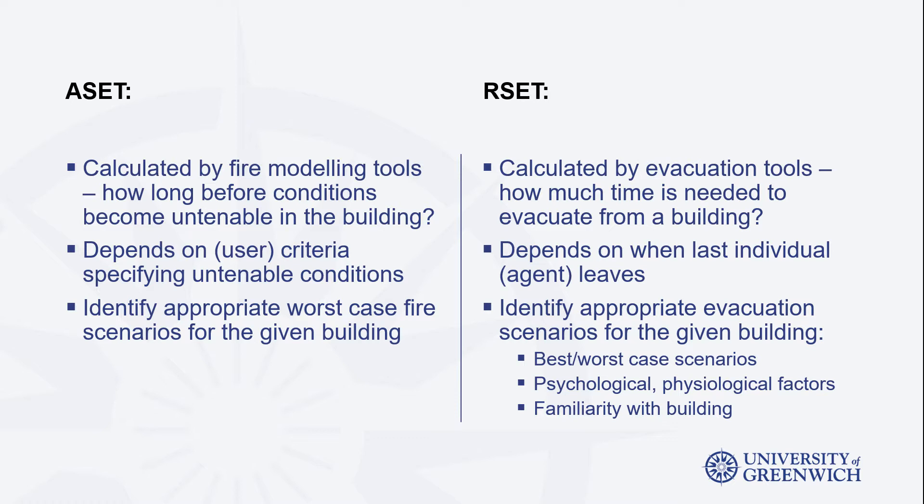For the first, the fire engineer would need to calculate the available safe egress time, or ASET, for specific fire scenarios of concern. These are normally calculated using a fire model, and the answer would equate to the minimum time that the conditions within a structure become untenable. The tenability limits within the structure are set by the user and could relate to specific temperatures being reached or to concentrations of toxic fire gases such as carbon monoxide.